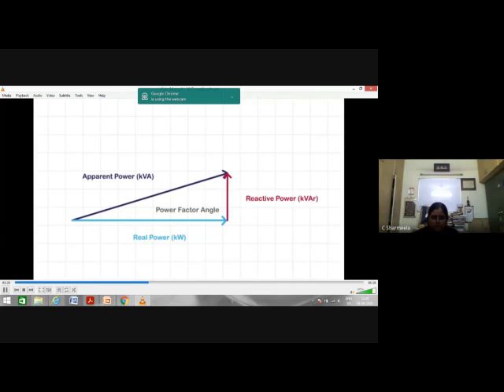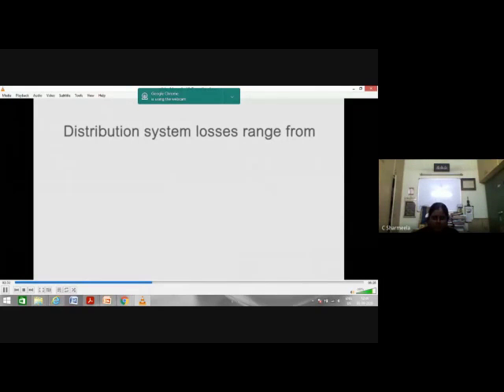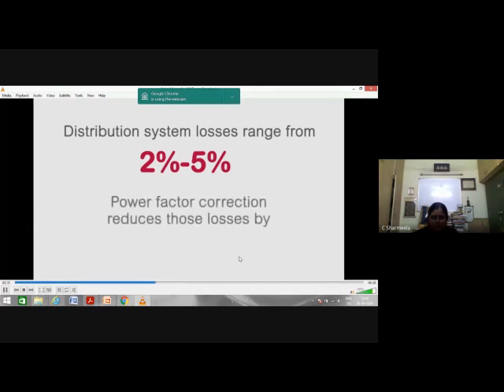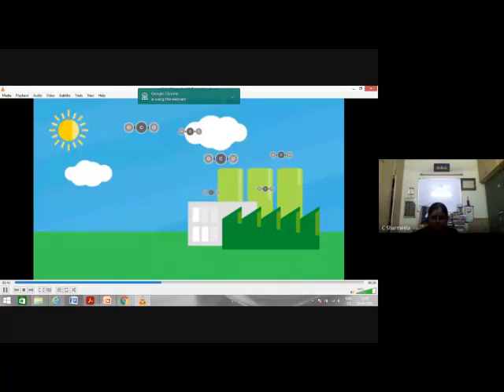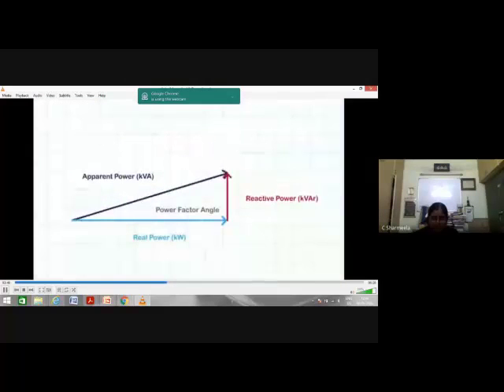Reduces I2R losses. Electrical distribution systems have losses ranging from 2% to 5%. Correcting power factor reduces the losses by 1 to 2%. Reduces carbon emissions since we reduce the I2R losses. Improves voltage regulation by correcting the power factor. We reduce the loading on the network, therefore reducing the voltage drop across the network impedance.